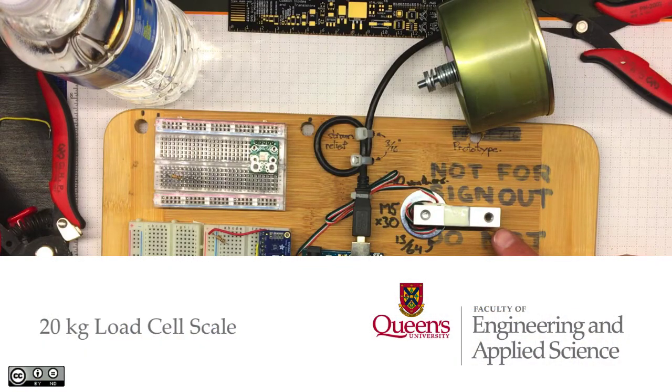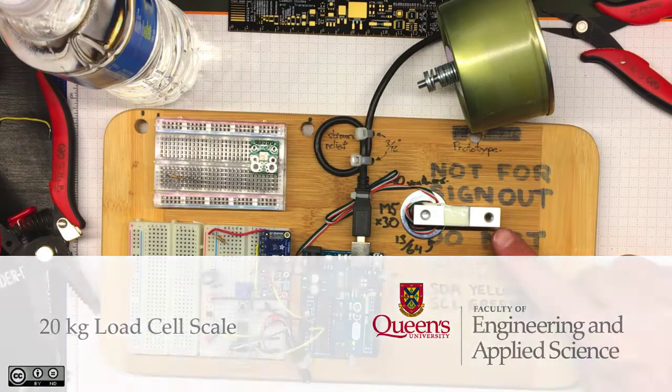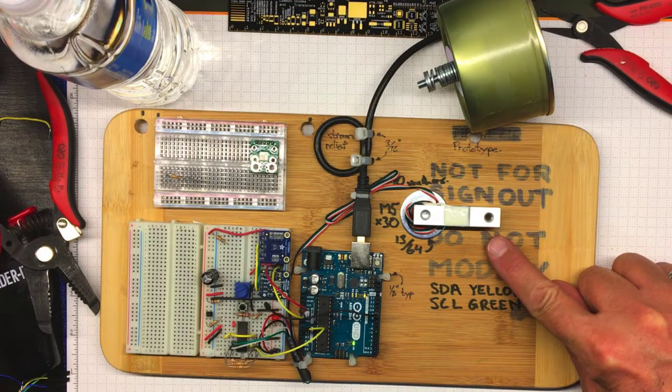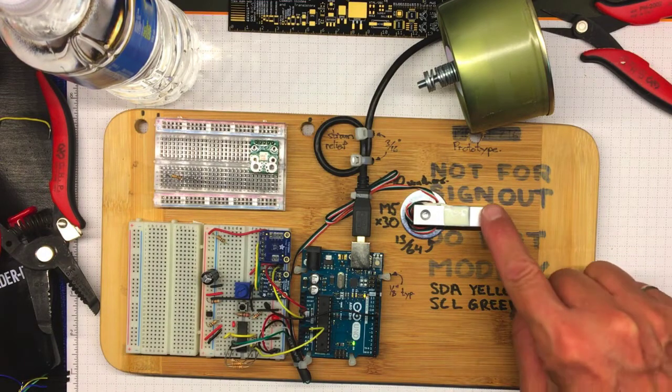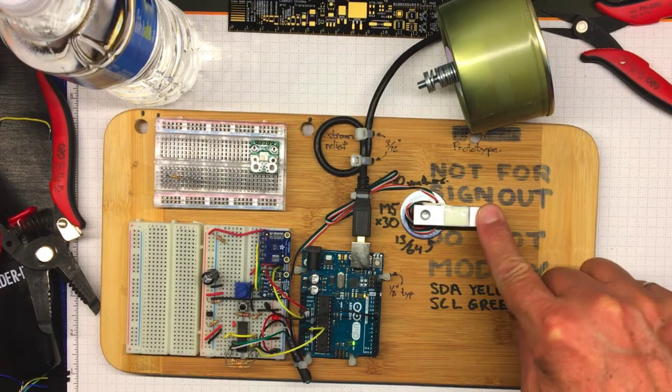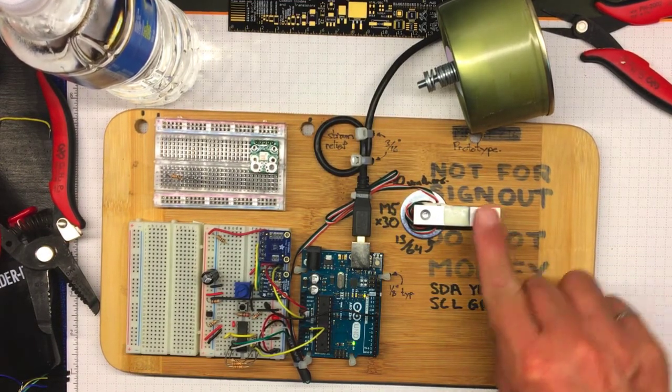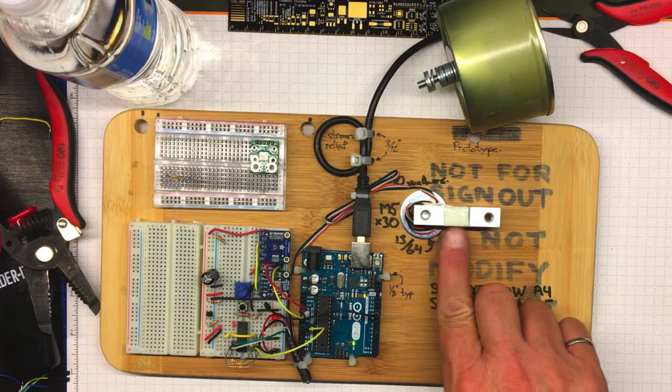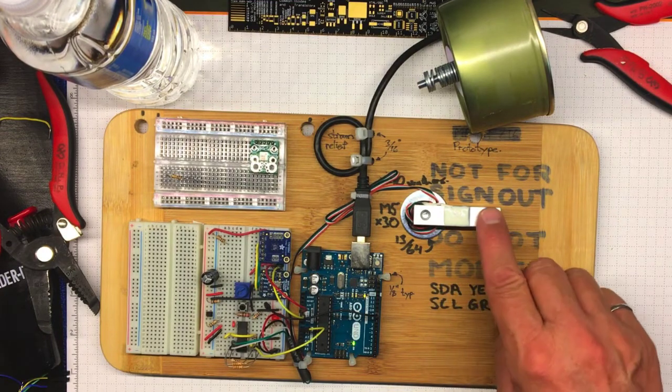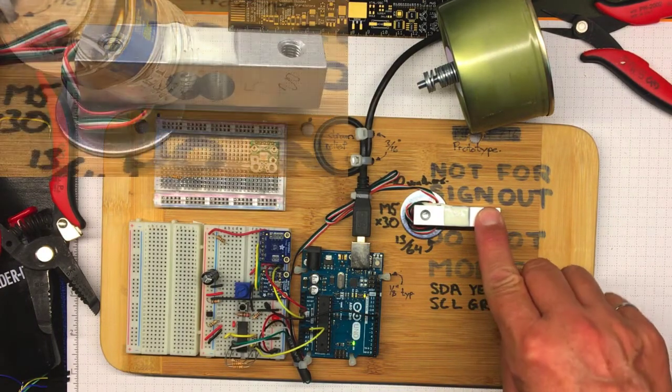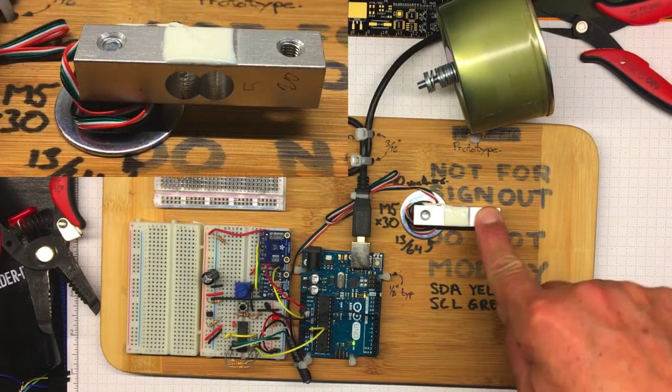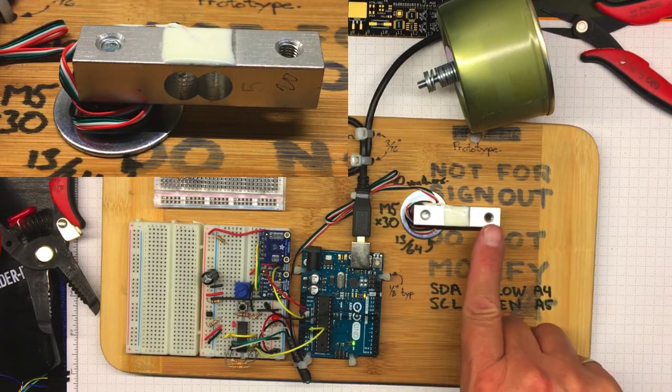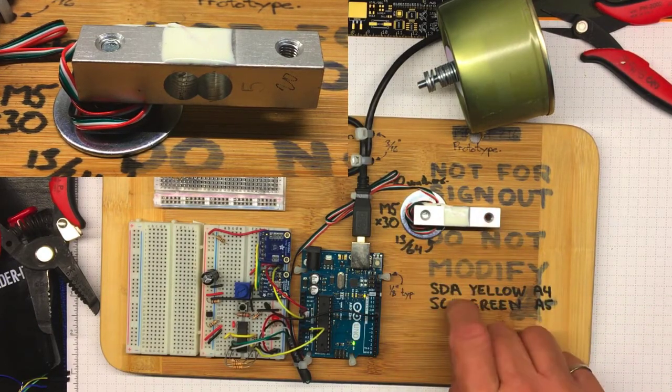This little shear beam load cell is set up with a lot of the same features that we use with the cantilever beam load cell in the lab, except it's a lot smaller and a lot stiffer. Because it's a shear beam configuration, it's sensitive to the applied force rather than to the bending moment.